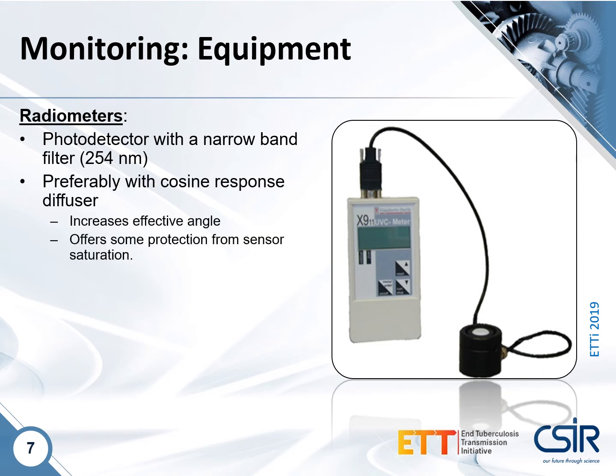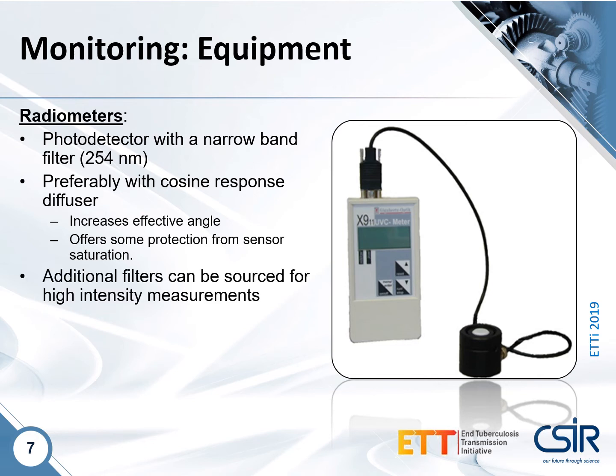Your radiometer should preferably include a cosine response diffuser. That cosine response diffuser increases the effective angle, making the devices more usable, and they also offer some protection from sensor saturation for very close-up measurements and other types of applications of UV. Additionally, filters can be sourced for high-intensity measurements, for instance, if you're going to use the device to measure UV tunnels or surface disinfection systems.